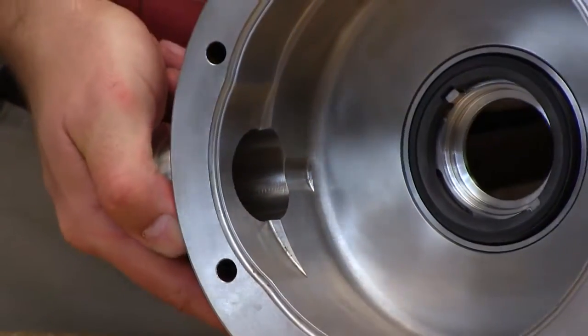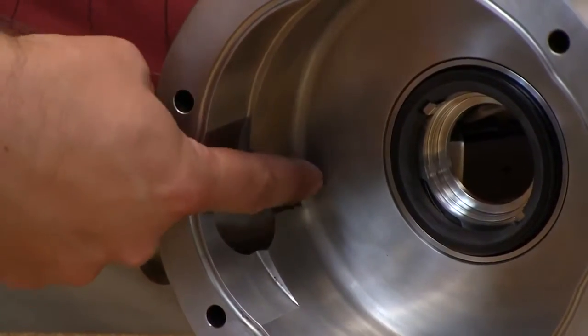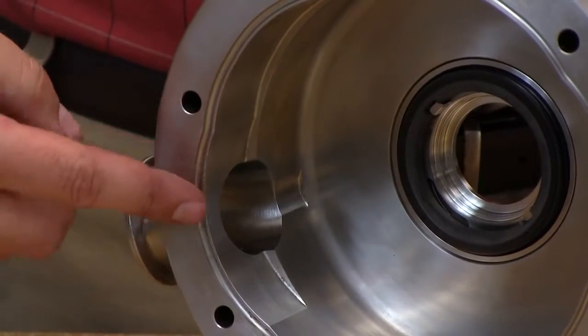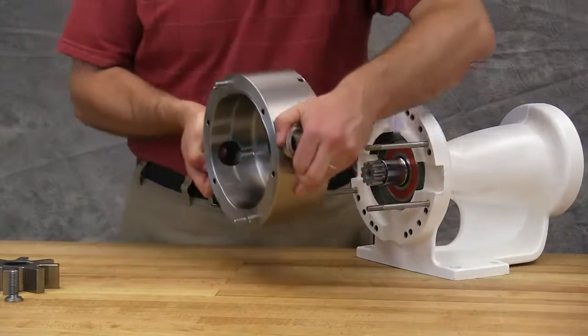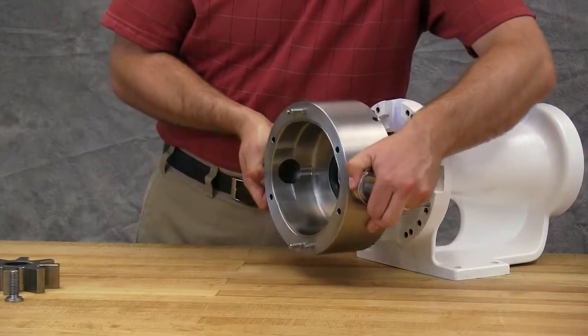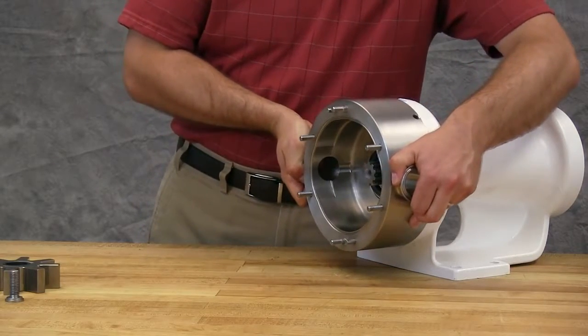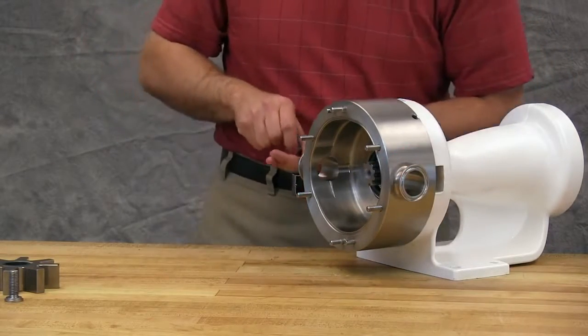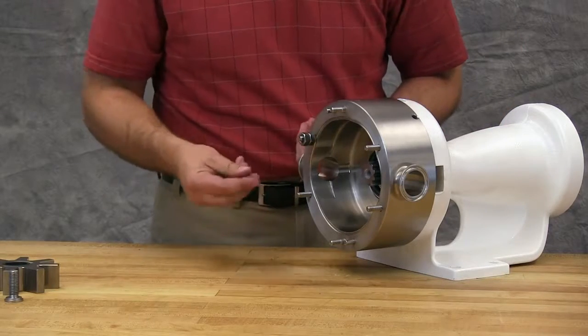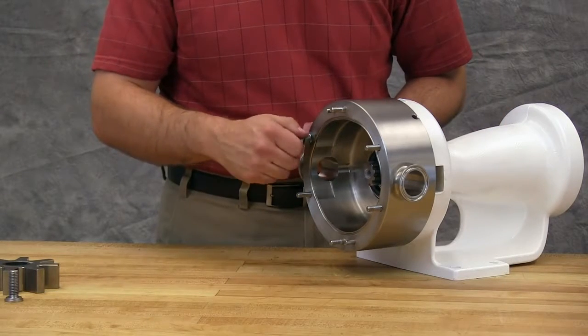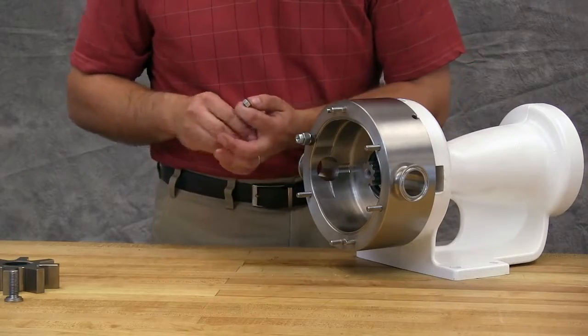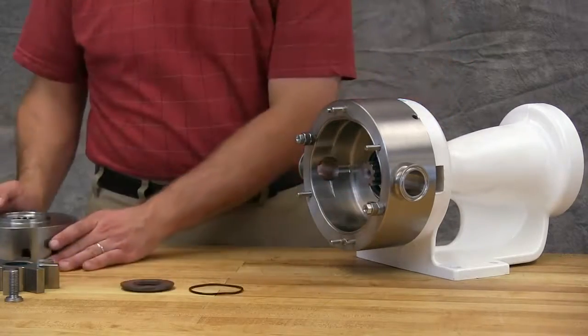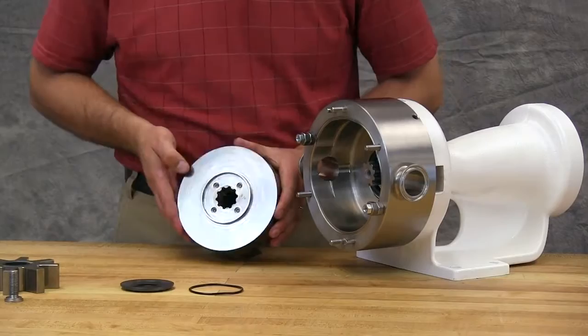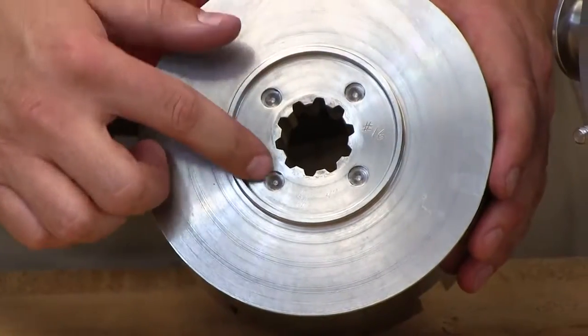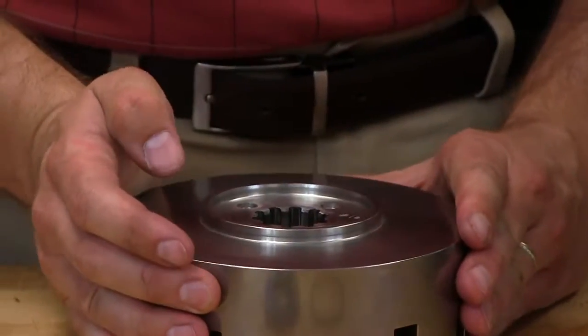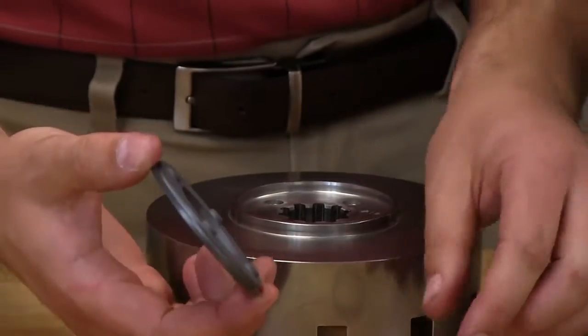The port with the casing groove needs to be used as the suction port for the pump's primary rotation. Use the casing studs to install the casing on the bracket. After installing the casing, use 2 nuts to hold the casing in place during assembly. The anti-rotation holes on the back of the rotor must line up with the lugs on the backside of the rotary face.